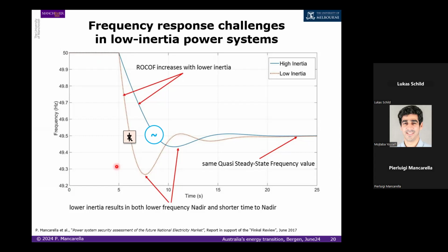Normally, when we talk about frequency stability, we're worried about a rate of change of frequency in the order of 1 hertz per second. So the frequency going down from the normal 50 hertz to 49 hertz in 1 second is really something we need to avoid. In the case of the blackout, the rate of change of frequency was in the order of 6 or 7 hertz per second. There's absolutely nothing that can be done when you have such a fast frequency collapse.